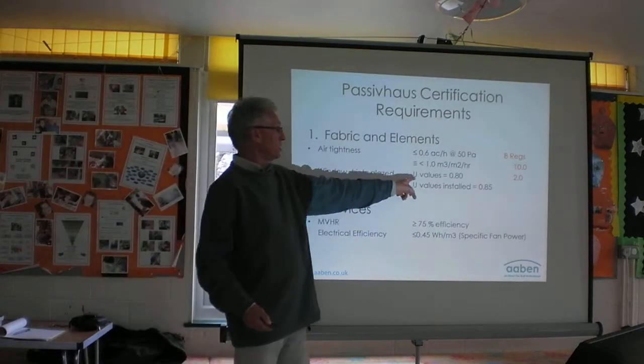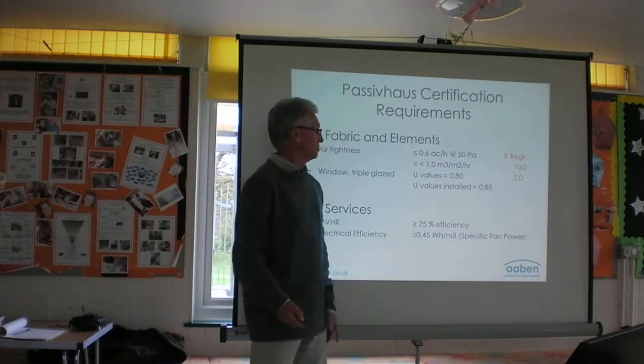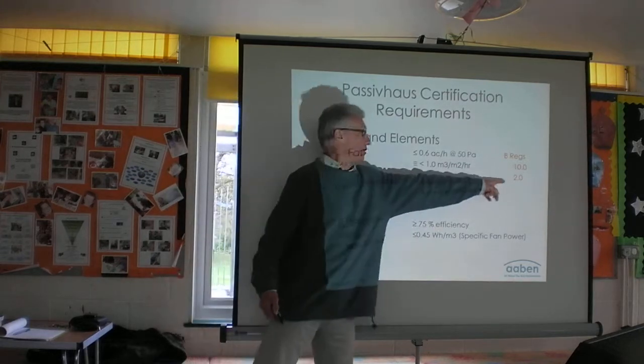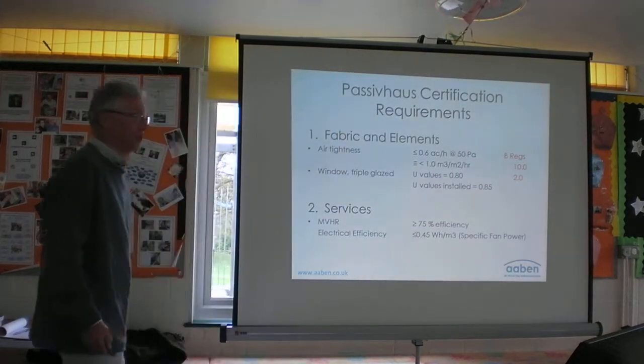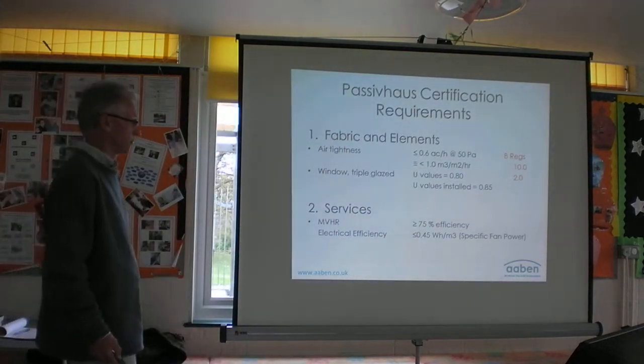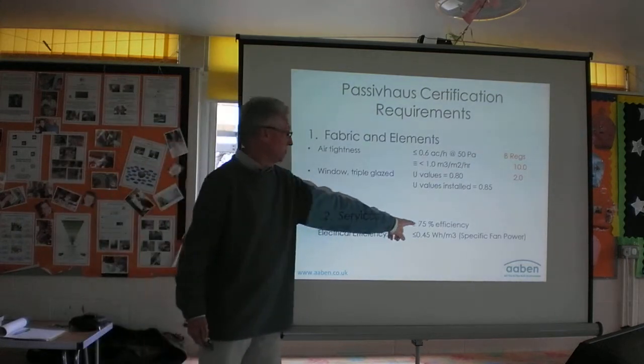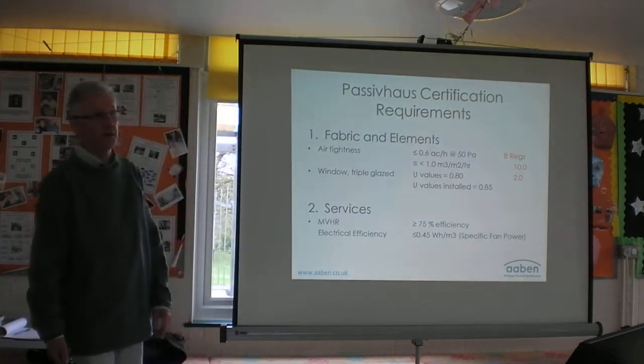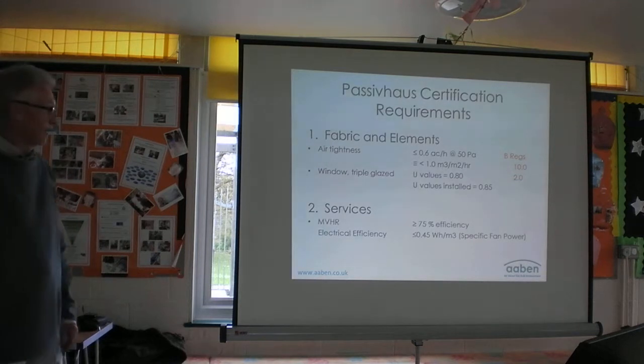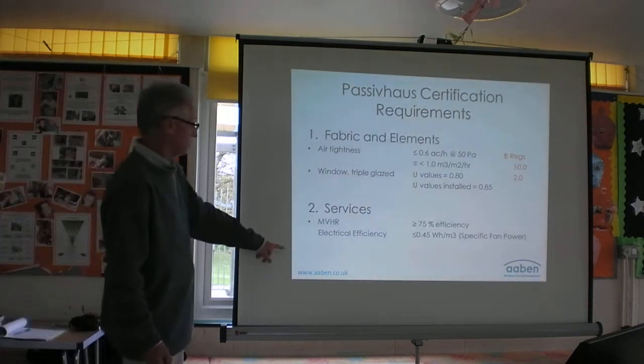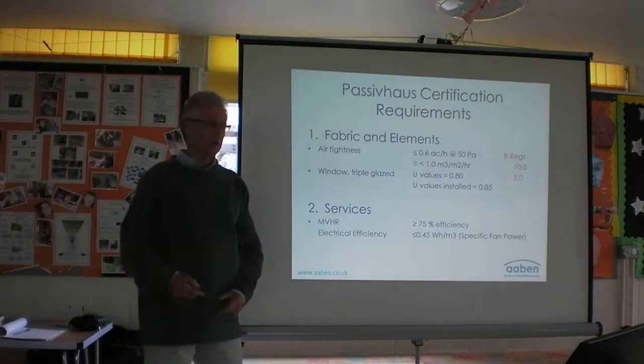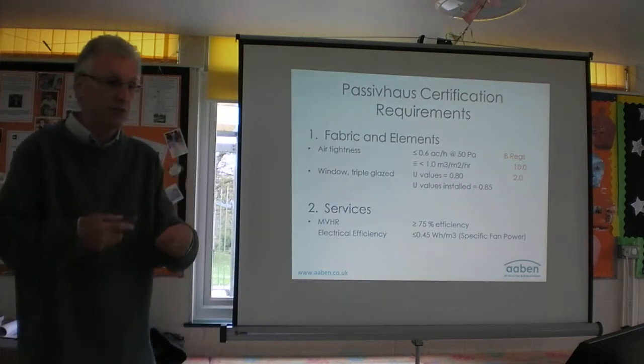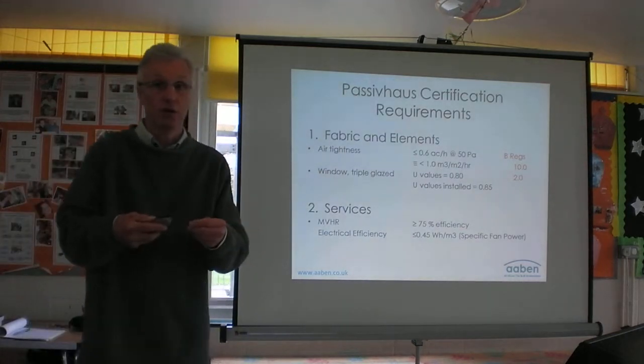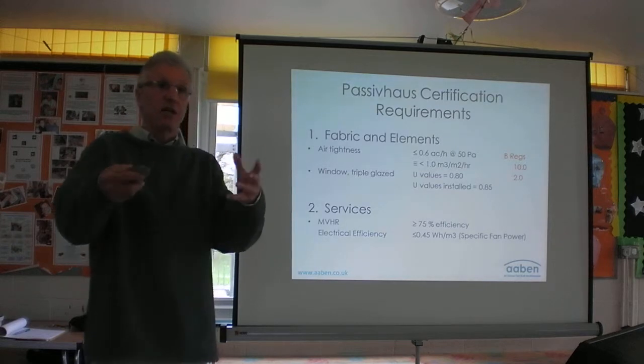We've got to put in triple glazing with U values of about 0.8 or below. Building regs 2, so it's more than twice as good in terms of the glazing. We've got to put in at least 75% efficient MVHR system, and it also has to have a low fan power. So when this is working, it's using much less energy to work than the energy it's recovering from the air.